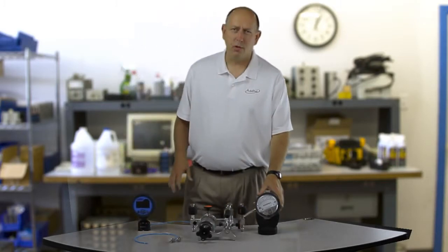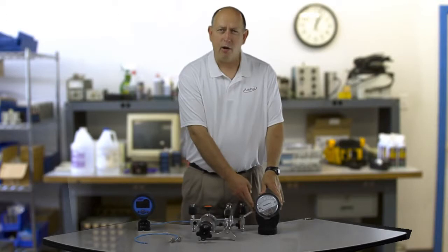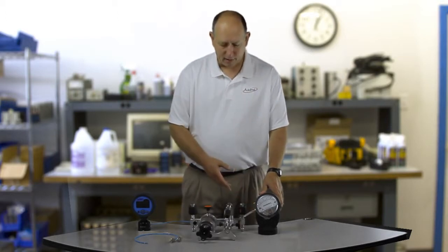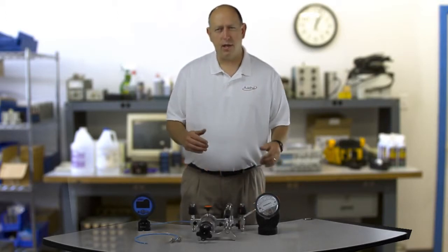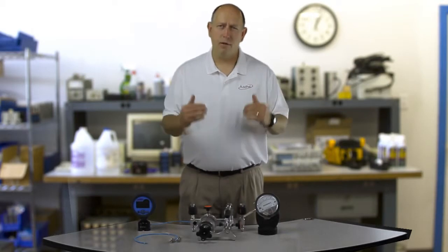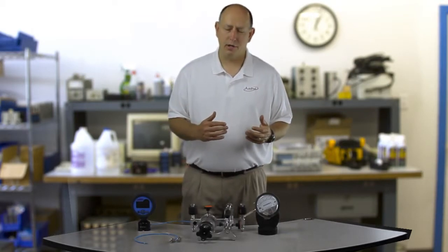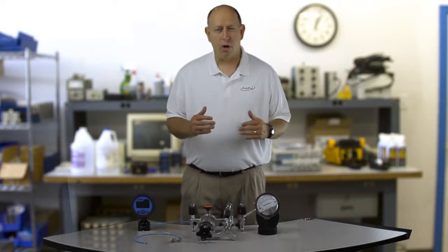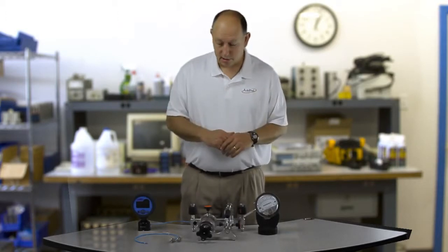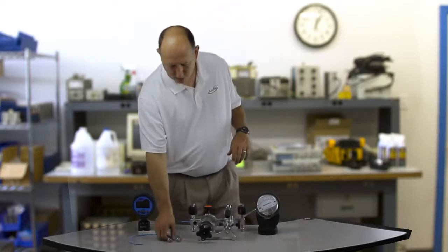A lot of customers will leave the low side open when doing a Magnehelic pressure gauge, but the problem with that is it will fluctuate with changes in barometric pressure. Since these are such small changes, that can be a significant error. So I've tied the low sides together.